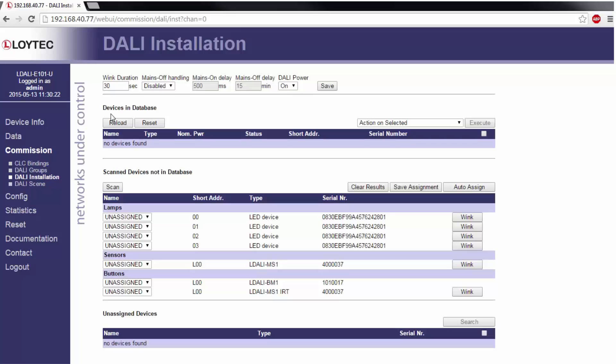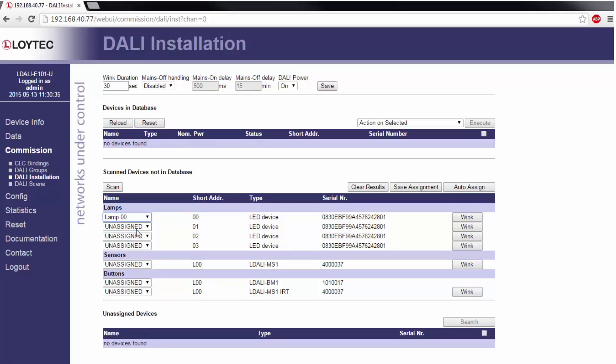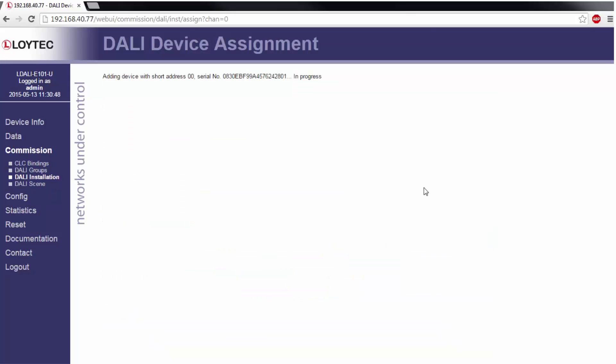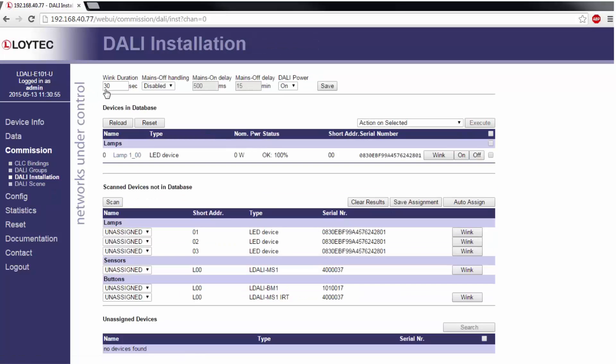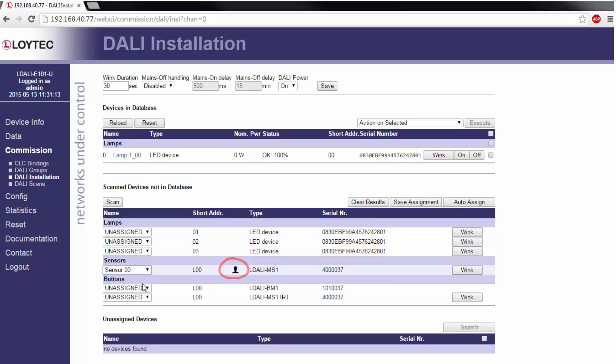By using the wink button you can identify the different devices. If using the wink button with a ballast the lamp will blink. If using the wink button with a sensor the LED of the sensor will blink. Sensors also will show you which sensor has detected the last movement. In case of push buttons the web interface will show you which button was used last.